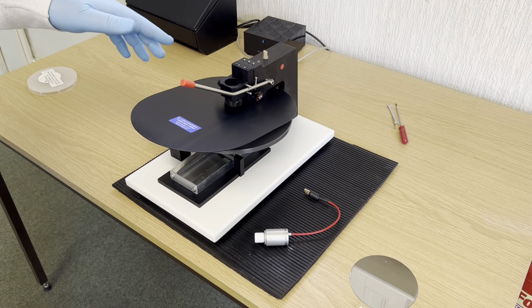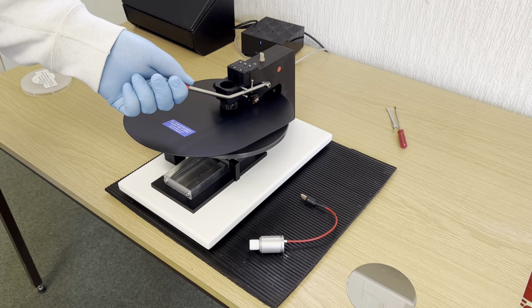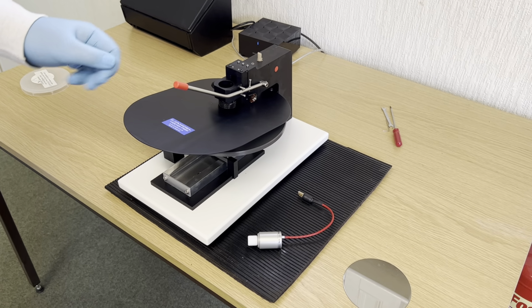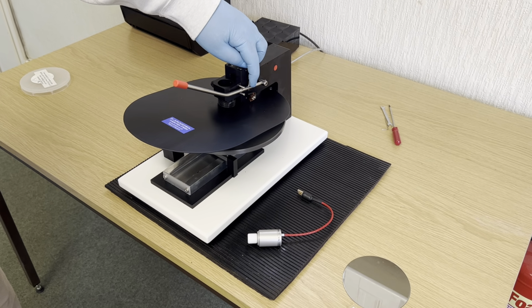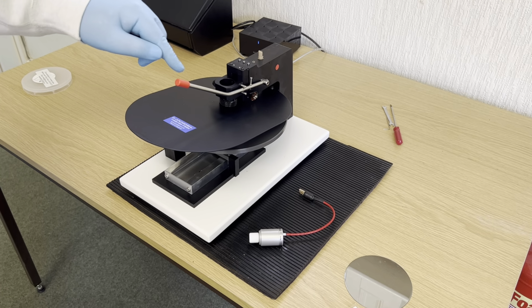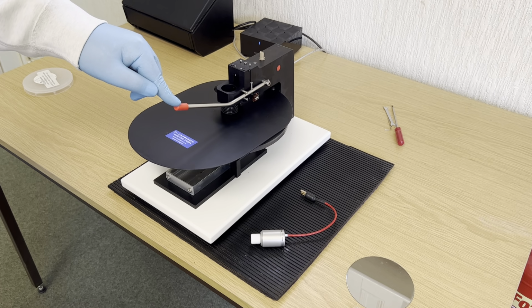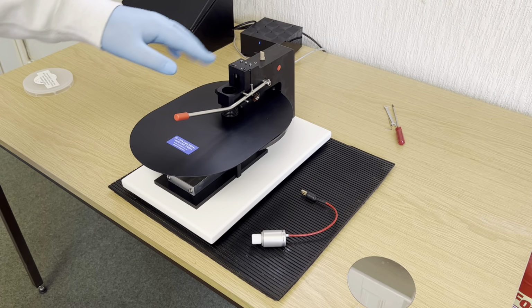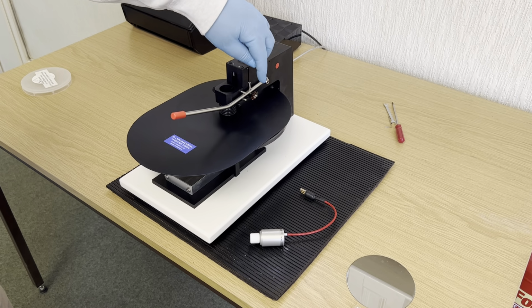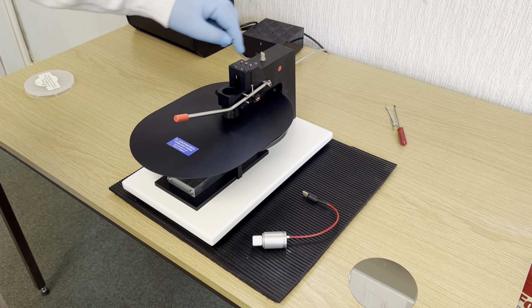This is the multi-position probe. The probe holder is raised at the moment. The first thing to do is ensure that the micro switch is set correctly. So we lower the probe until it stops moving. The micro switch shouldn't have activated at this point.